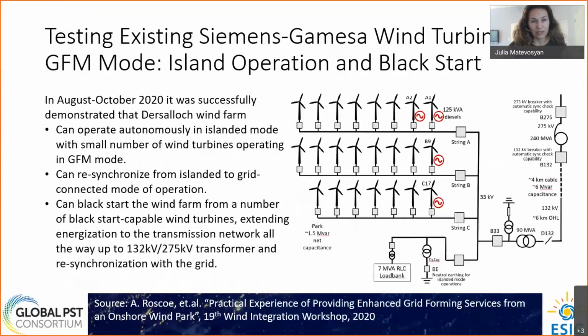All right. So the next test that they've done on that same wind farm in fall 2020 was to demonstrate islanded operation and black start operation. In this case, they were able to show that a wind farm can operate autonomously in islanded mode. They tested all the way from all wind turbines operating in grid forming mode down to a very small number of wind turbines, just trying to understand how small a number is needed. And they were able to determine that very few wind turbines need to be in grid forming mode for an island to operate successfully.